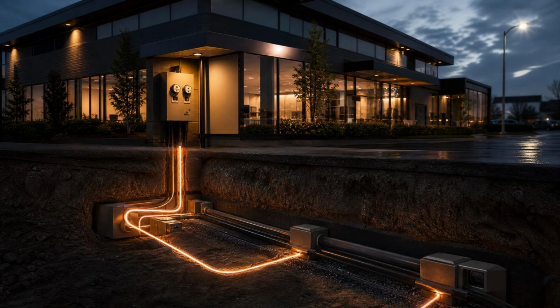The monitoring system also helps make a distinction that matters quite a lot in emergency power design. There is a difference between a brief flicker and a true outage, between a momentary sag in voltage and a genuine loss of the utility supply, and the monitoring system is designed to help separate one from the other. Power systems flicker. It is simply part of how they behave. A heavy motor starting somewhere on the same circuit can pull the voltage down for a fraction of a second. A distant fault that is quickly cleared can cause a brief interruption.